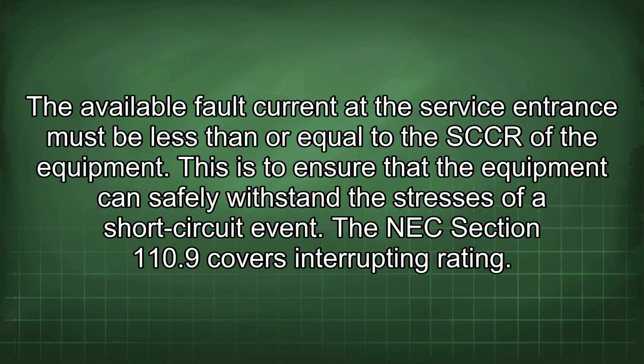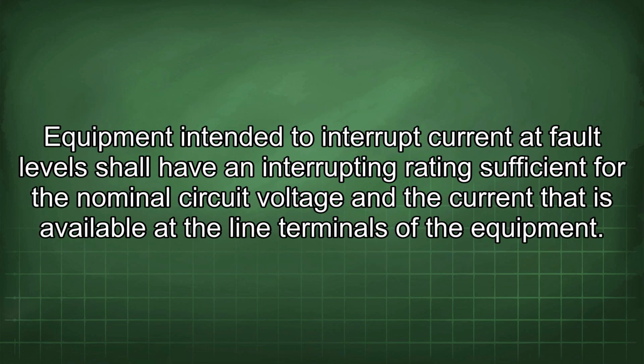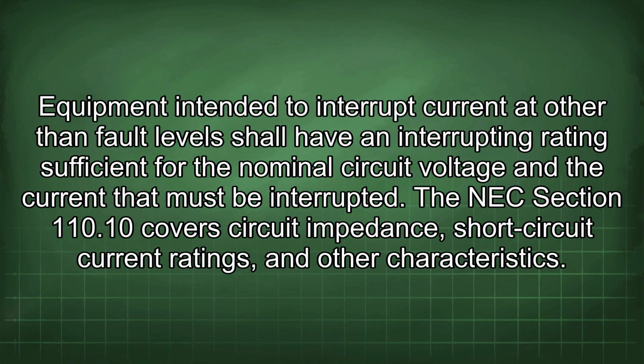The NEC Section 110.9 covers interrupting rating. Equipment intended to interrupt current at fault levels shall have an interrupting rating sufficient for the nominal circuit voltage and the current that is available at the line terminals of the equipment. Equipment intended to interrupt current at other than fault levels shall have an interrupting rating sufficient for the nominal circuit voltage and the current that must be interrupted.